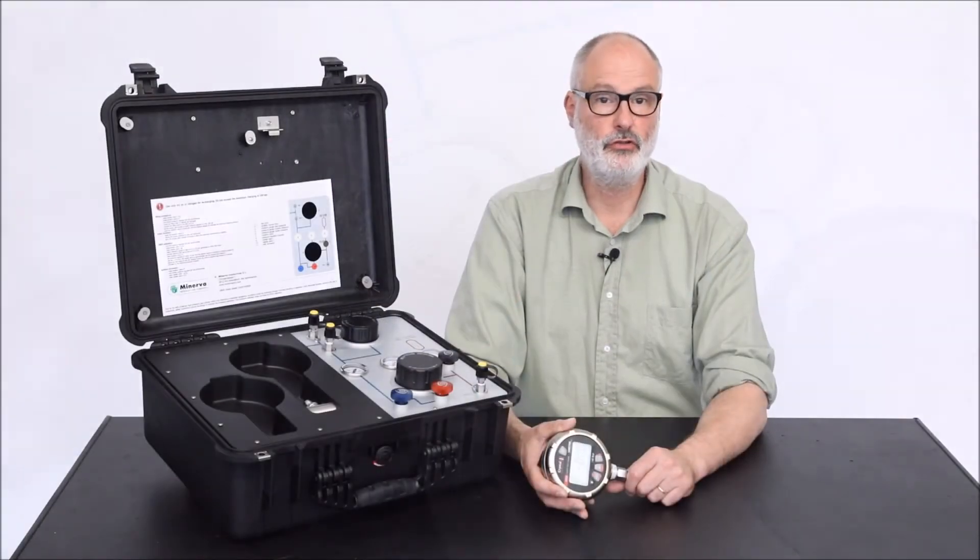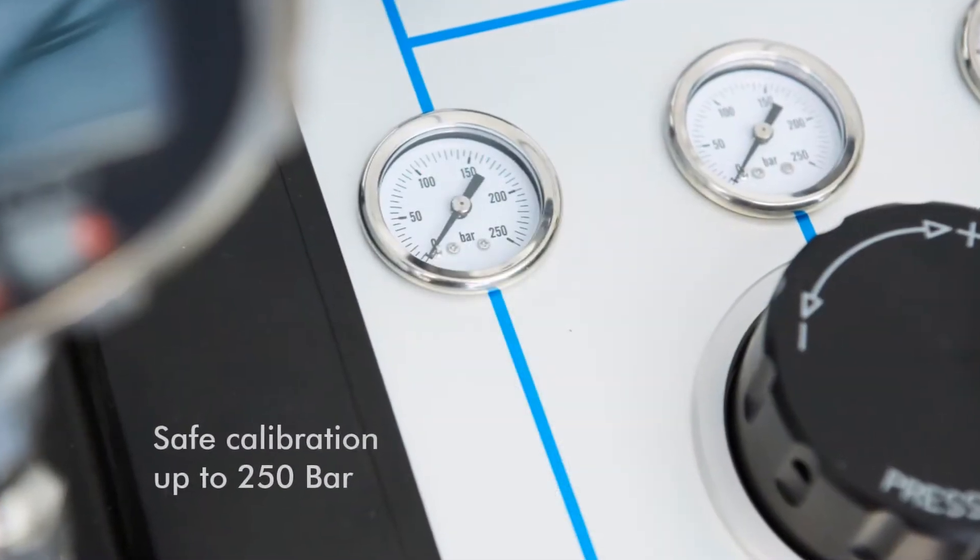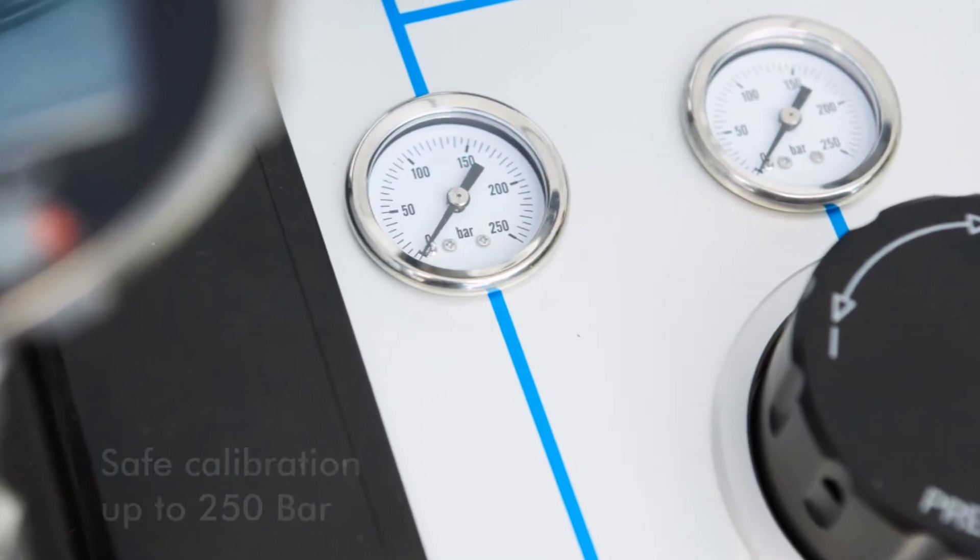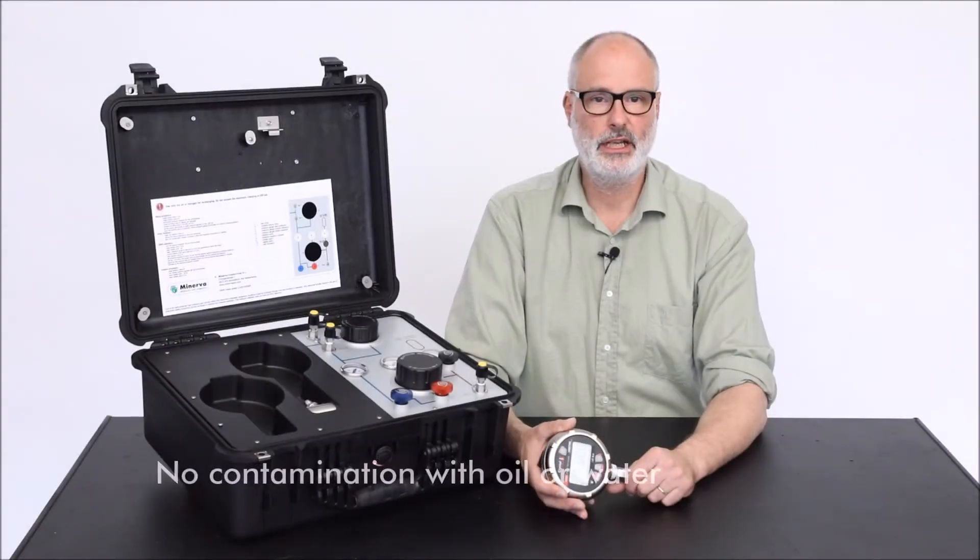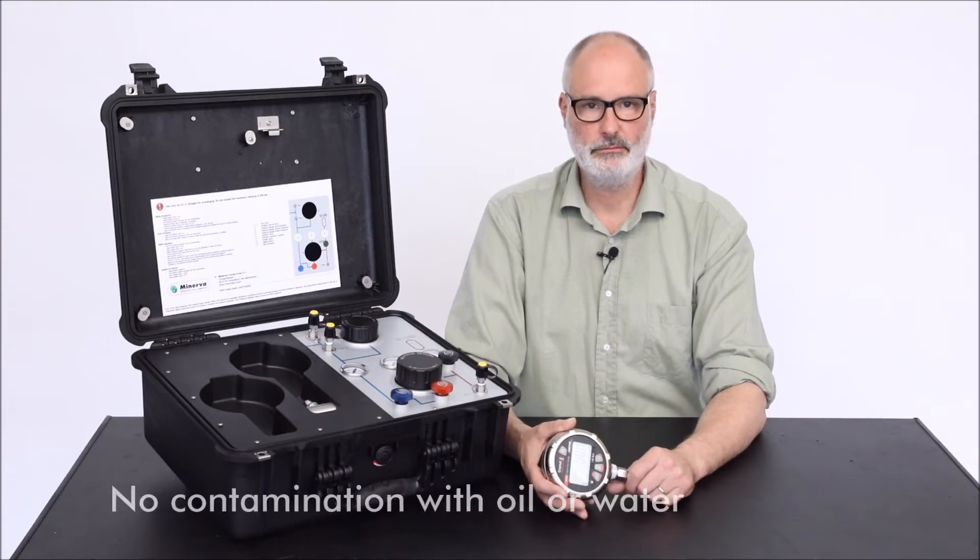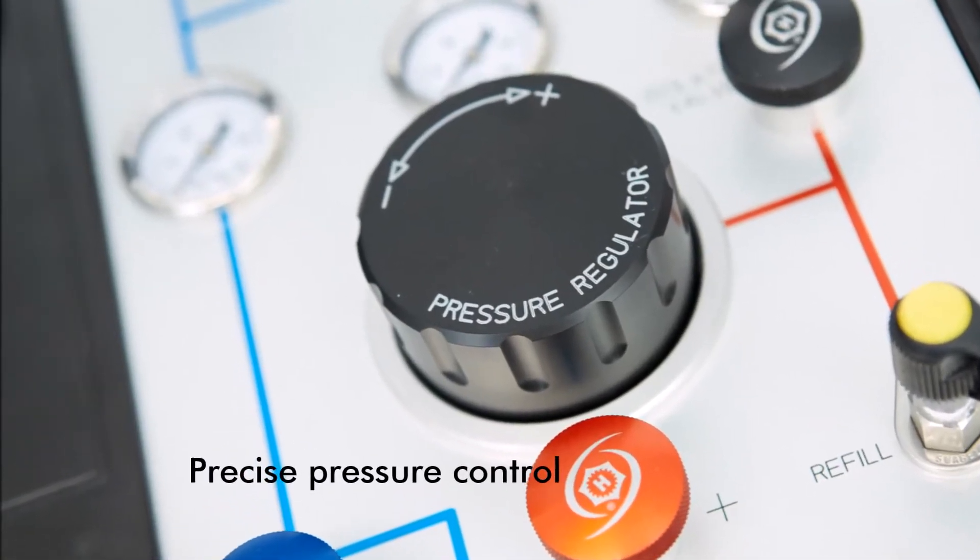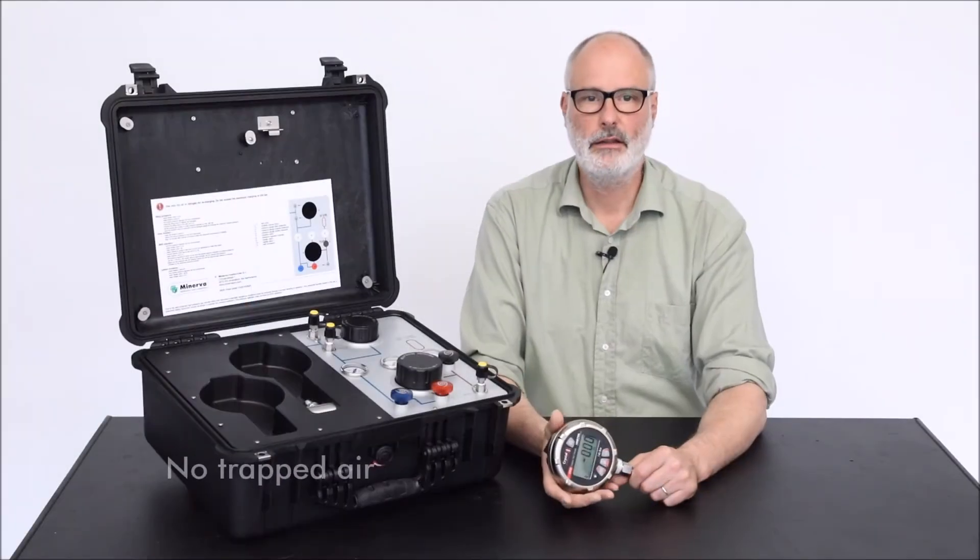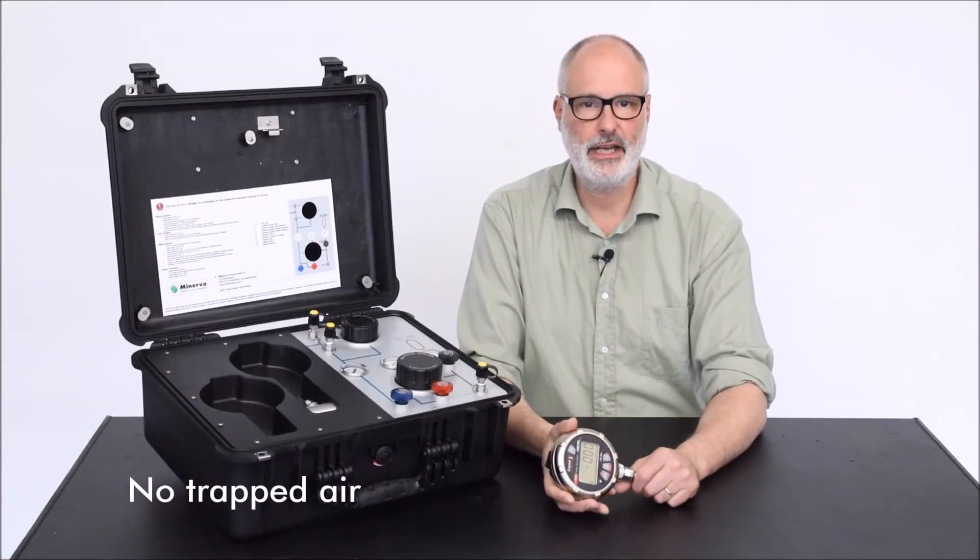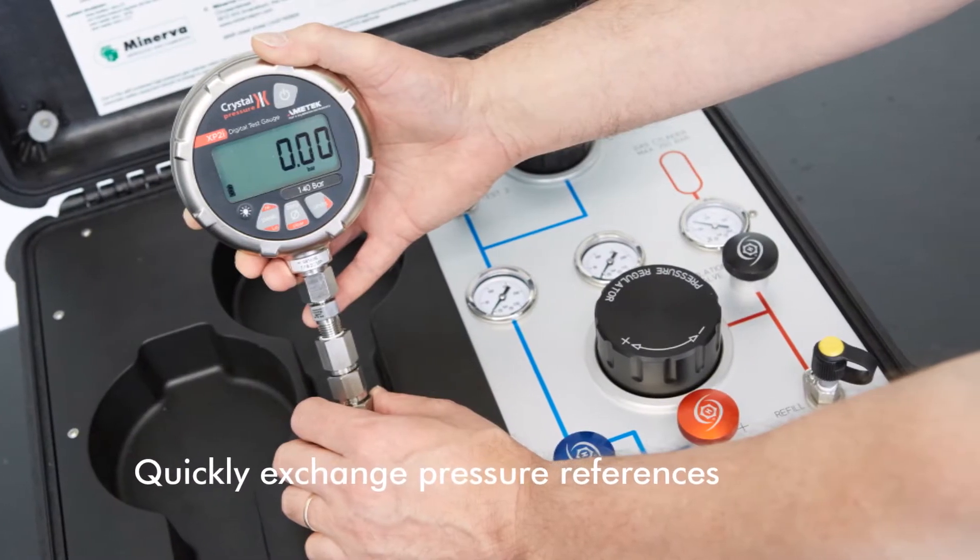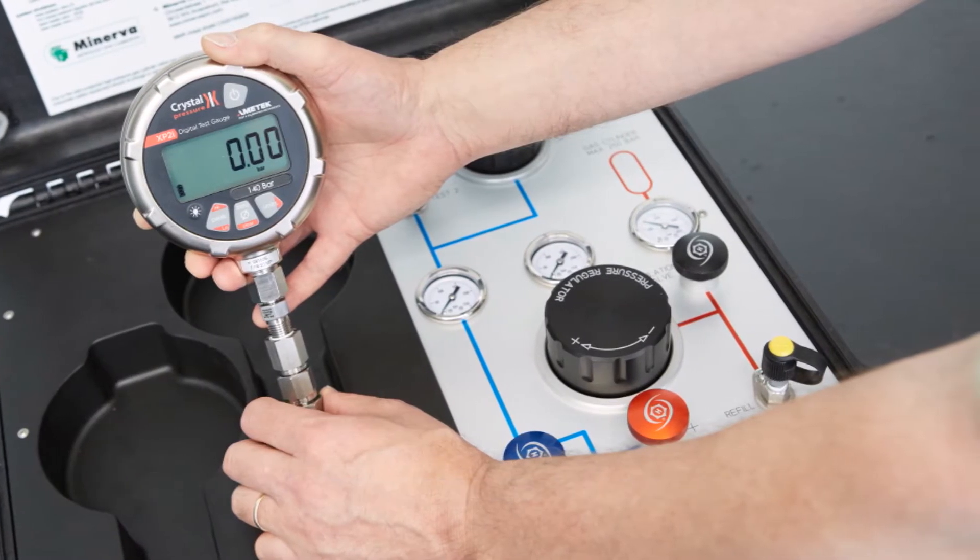This case enables you to perform safe pneumatic calibrations up to a maximum pressure of 250 bar, not contaminate the device on test with oil or water, perform precise test pressure control using a pressure balance volume adjuster, eliminate trouble with trapped air in hydraulic systems, and exchange calibrator pressure references quickly and easily.